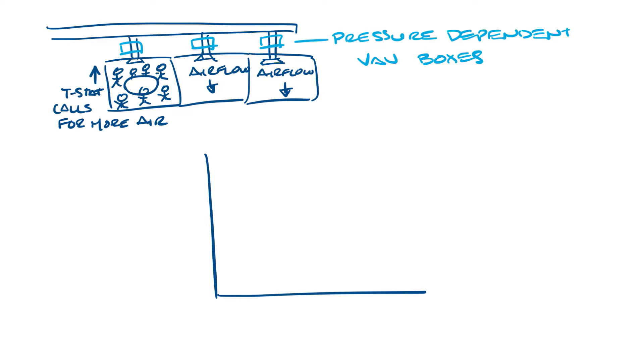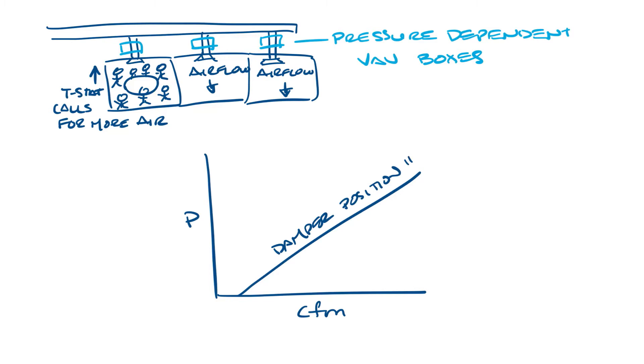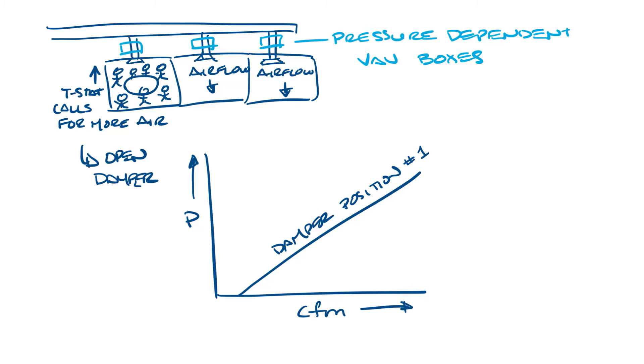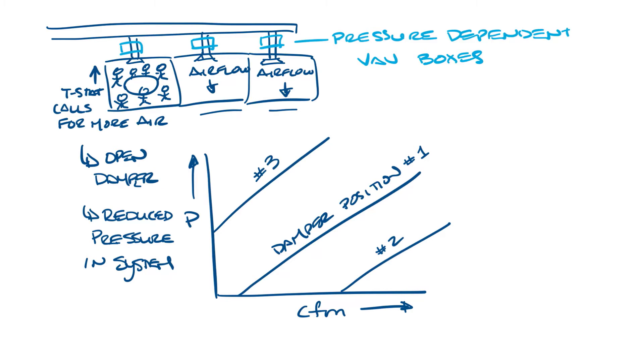If you were to graph airflow versus pressure in a pressure dependent VAV box, it would look something like this. For any given damper position, as the pressure goes up, the CFM goes up, and as the pressure goes down, the CFM goes down. So as the system pressure decreases, like in the example with these offices when the conference room damper opens, the airflow goes down. And if you had damper position two or three, the same thing would happen.